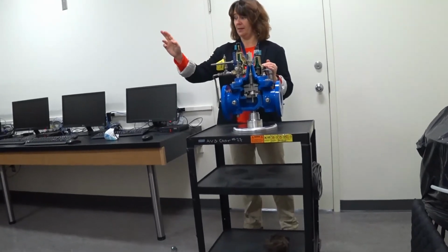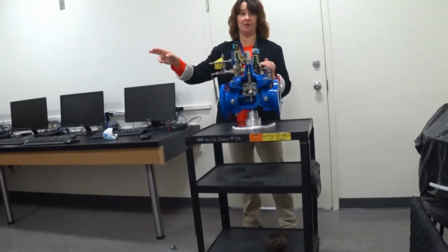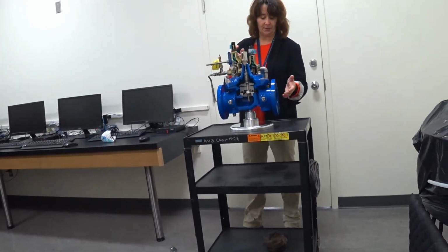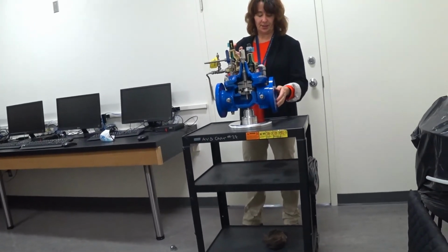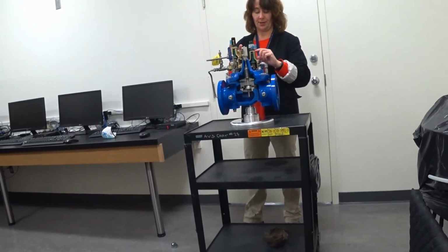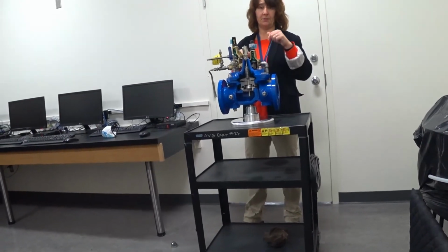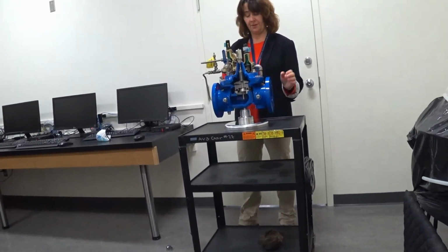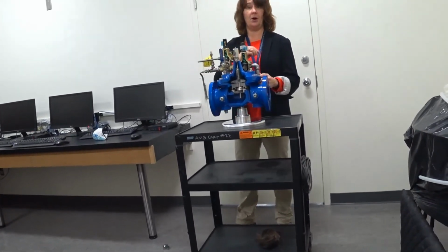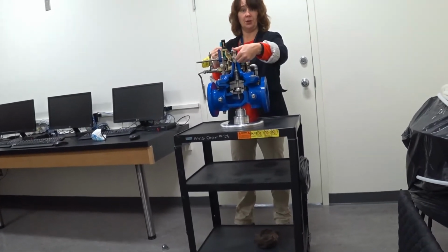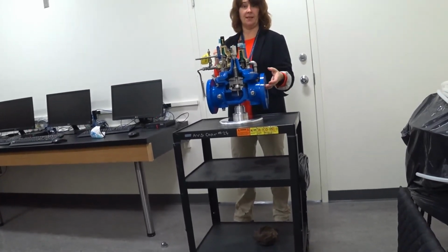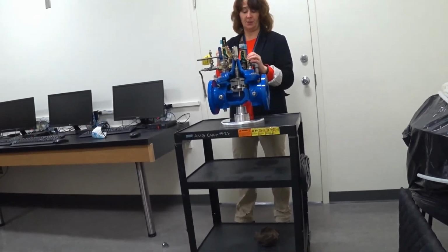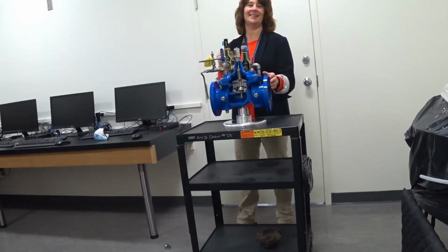So in that way, it works exactly the same as the CRD function on the red valve, exactly the same. And in the same way, when you have low downstream pressure here, basically the spring force will then win, which allows the stem to travel down, which opens this valve, which allows all that 0.1 gallons per minute off. And it will also start to pull water from the top of the bonnet, which allows the main valve to open. And then you have less pressure losses, so the downstream pressure will rise. Okay? So this one is all about trying to maintain a set downstream pressure.